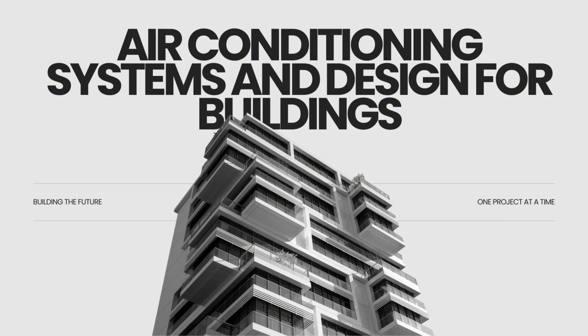Got it. So unitary first, the window box. Right. The unitary air conditioning system is what most people recognize as a window-type air conditioner, or sometimes a through-the-wall air conditioner. It's essentially a self-contained air conditioning unit within a single cabinet. All the necessary components, the compressor, condenser coil, the evaporator coil, the fan motor, they're all integrated into one compact box. This makes them quite distinct from other systems, as the entire refrigeration cycle happens within that single enclosure. So everything is literally in one unit, making it a fairly straightforward setup. What are the practical upsides and downsides of having everything bundled together like that? And how do designers account for its presence?